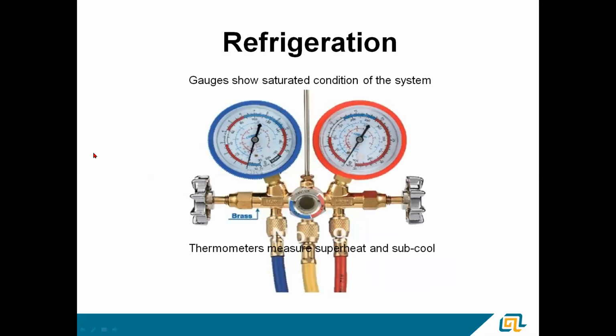So a little bit about refrigeration. Not going to spend a lot of time on superheat and subcool. We've all done the calculations. We're all comfortable with them, I'm sure. Remember, the gauges show the saturated condition of the system. So if your suction gauge is reading 123 pounds and you got R410A in there, your indoor coil, if you lay your temperature probe on it, is going to be running about 42 degrees. Thermometers measure the superheat and subcooling, the actual temperature of the lines.